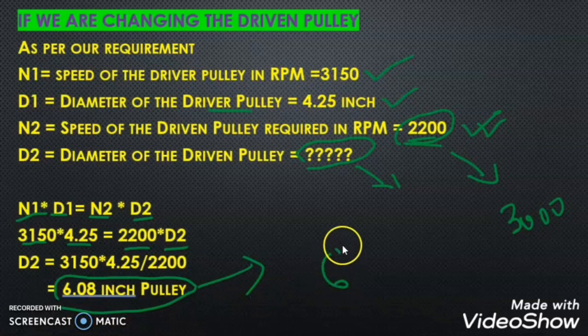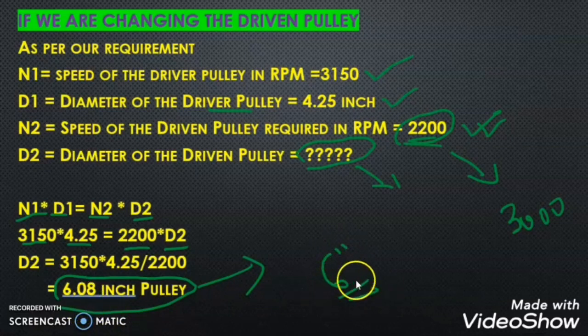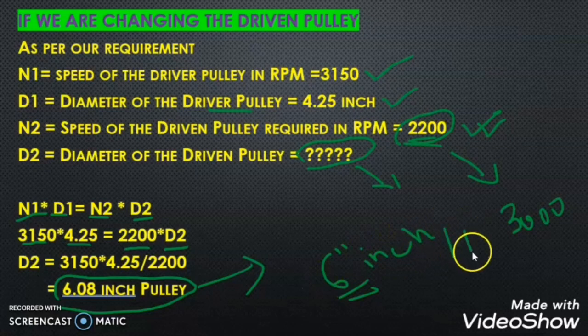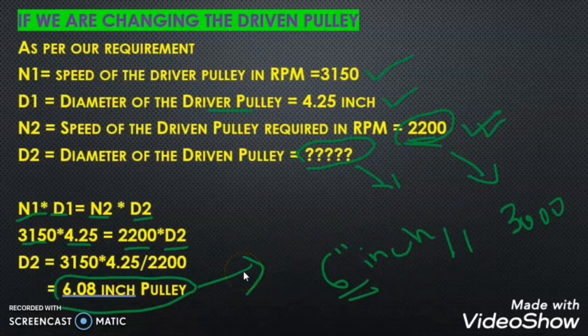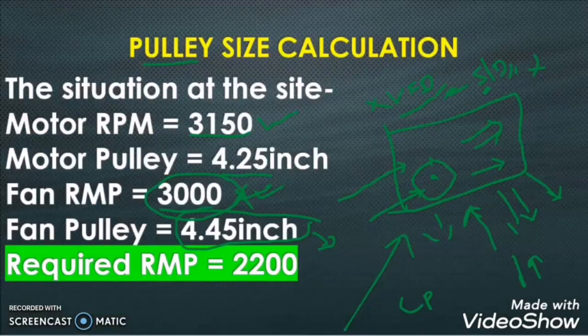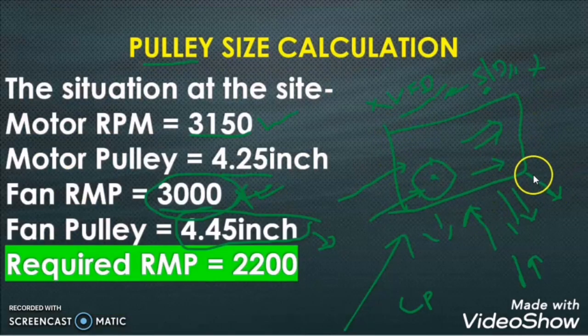The nearest available standard size is 6 inches, so we need to install a 6-inch pulley. We did exactly that, and we got the result — there is now no dripping of water from the FAHU.